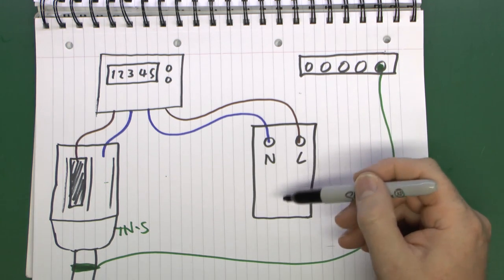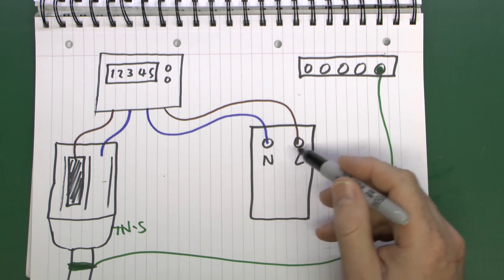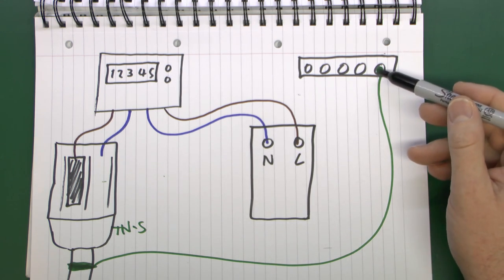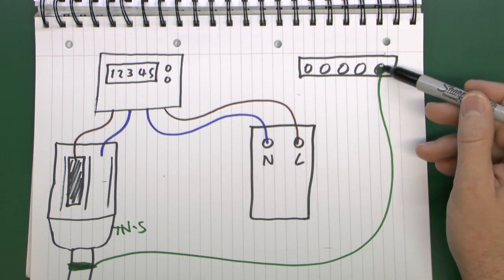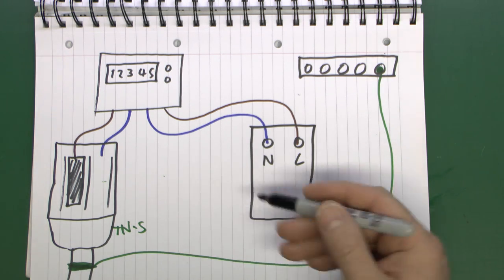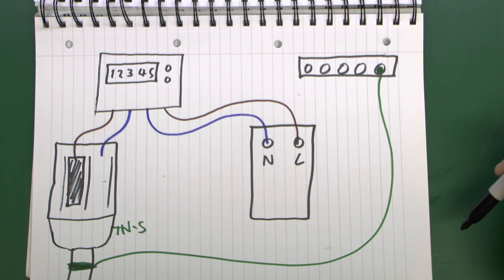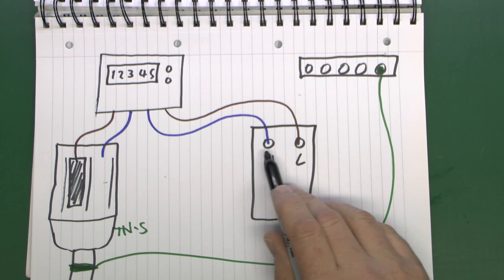Now before actually switching this isolator on here and energizing the installation, we need to make sure that the neutral and line are in the correct places and also that the main earth is actually connected. You would do a continuity test here between the earthing bar and the actual incoming point where the earth is connected. That's just comparing the continuity of that, it's a fairly simple thing. And then to check these two are connected correctly.